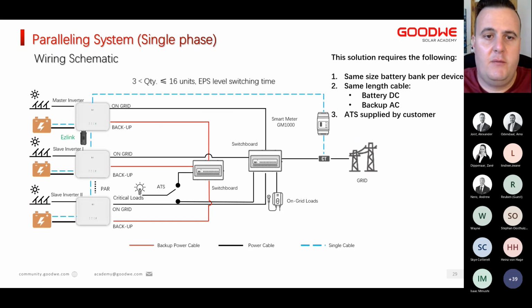Then lastly, on the parallel, we can parallel up to 16 units in communication. Please note this is all just in single phase currently. We are working on the 3-phase capabilities, but it's not yet available. With up to 16 units, you only have EPS level change over time. So with this one, the requirements are the same battery banks, the same AC cable lengths, and thirdly, an ATS. Currently you do require an ATS so that during normal on-grid operation, all the loads are connected to the grid side of the inverters. And when the grid fails, the ATS switches everything over to the backup side of the inverters.